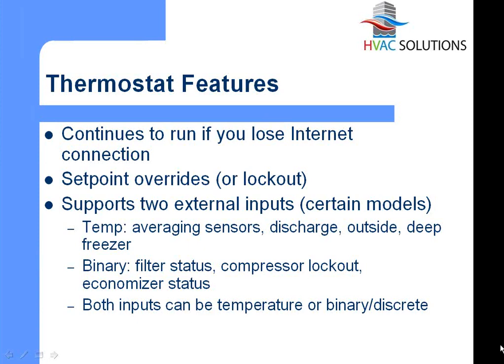You can put discharge sensors in on the ductwork, so if I call for heating, I can look and see remotely over the internet if my unit actually isn't heating because I have a discharge temperature that's, say, higher than 100 degrees. I can use it for outside air temperature monitoring. I can use it to monitor miscellaneous temperatures on anything that I want, even if it's unrelated to what I'm controlling with the thermostat. So in a restaurant, I may have the thermostat controlling the HVAC equipment, but maybe I want an extra sensor over in the walk-in freezer to make sure that temperature is okay too, and I can see that remotely over the internet.